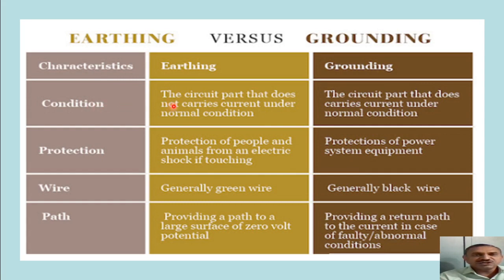Let us first see the condition. The condition in earthing is that the circuit that does not carry the current under normal working condition is connected to the earth through the earth electrode, while in grounding the part of the circuit which carries the current under normal working condition is connected to the earth. The second characteristic on which we can compare is the protection. The protection in case of earthing is for the people and animals from an electric shock if they are touching that particular equipment. For grounding, the protection is provided for the power system equipment also. So that is the difference.